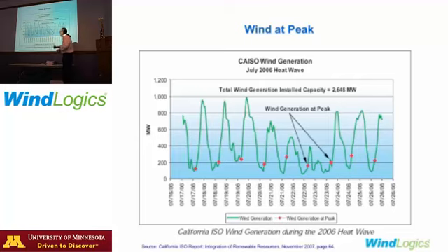And the red dot is their peak load hour. What you see is that the winds definitely were not at their best at their peak load hour in the late afternoon. They weren't zero, though. They were roughly 10% of the nameplate. So it wasn't zero, but this is kind of the capacity value approximation, right? The contribution toward your critical hours, and often for wind, it's in that 10 to 20% range, the way we calculate that.